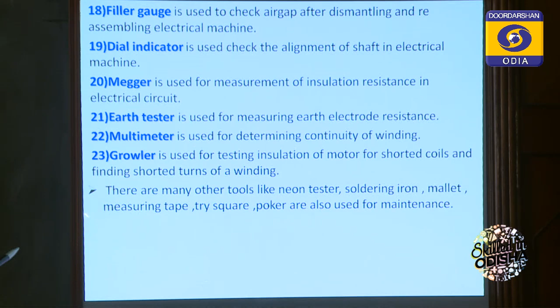Standard wire gauge is used for determining the size of cables. Feeler gauge is used when we dismantle a machine and again have to mount it; we check the air gap with the feeler gauge. Dial indicator is used for alignment of shafts in electrical machines. Megger is used for insulation resistance checks. Earth resistance is checked by an earth tester. Multimeter is used for determining the continuity of winding. Growler is used to identify short circuited coils in a winding.